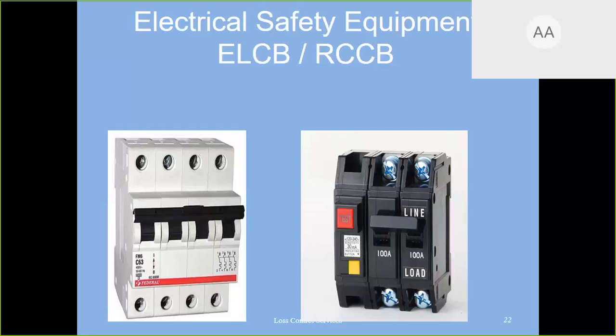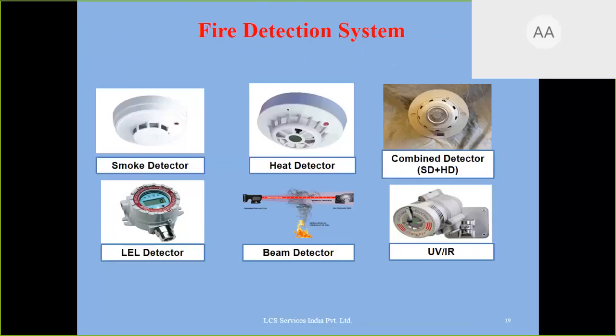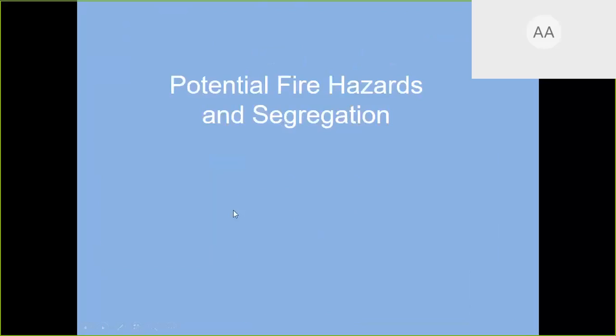So in the machine also it can be installed. All CNC machines, you can install RCCB, and in each distribution board we can install ELCB. It is not very costly. It is like MCB. So MCB's purpose is different; ELCB is different. MCB will trip at overload. MCB is for the equipment safety. ELCB is for the human safety. Right? So various types of hazards are there. You have to segregate them. You have to provide the fire prevention equipment so that there is no fire. So this was my third topic, which is known as the fire potential hazards and segregation.